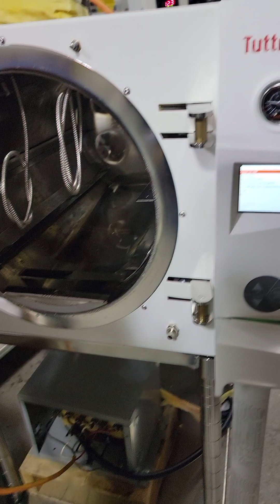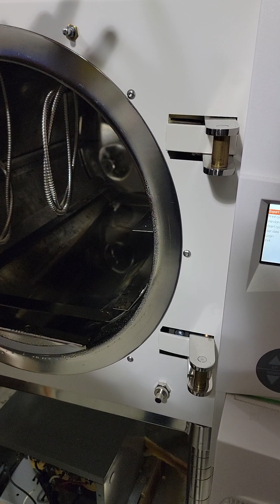Also, every 3870 requires a buck boost transformer somewhere in the circuit, because you have to have 230 volts stable. Can't do 208, 212, 224, whatever -- it's got to be stable, so you need a buck boost transformer. This bad boy isn't single phase like most 3870s, it's 3-phase. So this is the 3-phase 208 to 230 volt transformer. Yeah, about $600. Anyway, back to where I was.